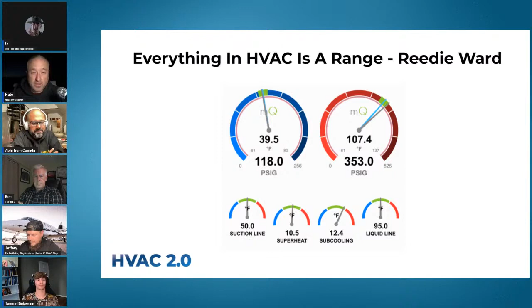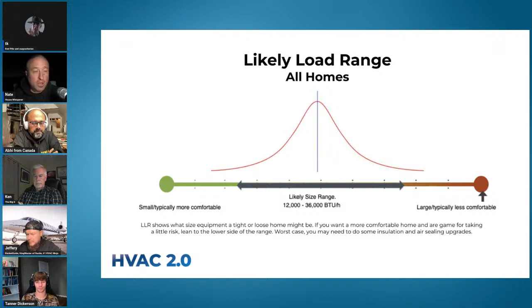What we'll talk about next week is what we call likely load range. If you don't understand the load of a house, it's going to fall in a fairly wide spectrum—for this one, I was imagining between 1 and 3 tons. The goal of likely load range, a calculation about to hit the HVAC 2.0 software, is that if you think of a bell curve, we're trying to cover the vast majority of what's under it—90 or 95% of likely heating and cooling loads.